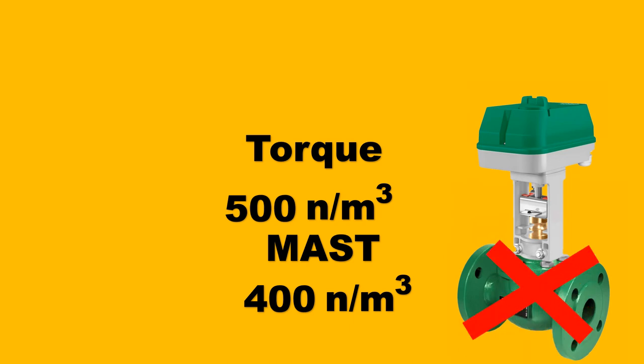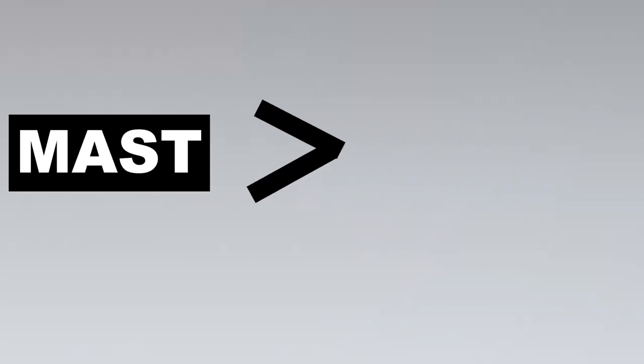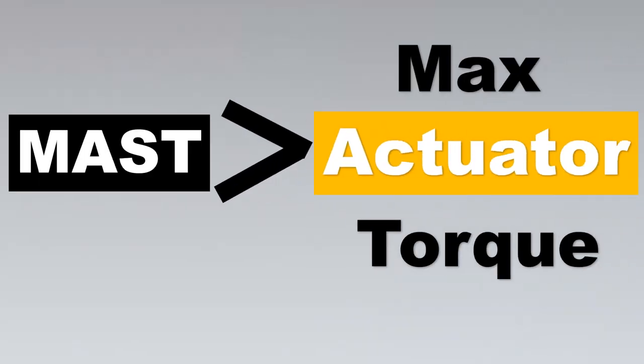The answer is no — it will destroy your valve. So we learn a very important equation to always remember for good engineering practice: your MAST must always be greater than the maximum actuator torque. This is to be noted in bold letters for every engineer who wants to design a plant in a safe fashion.